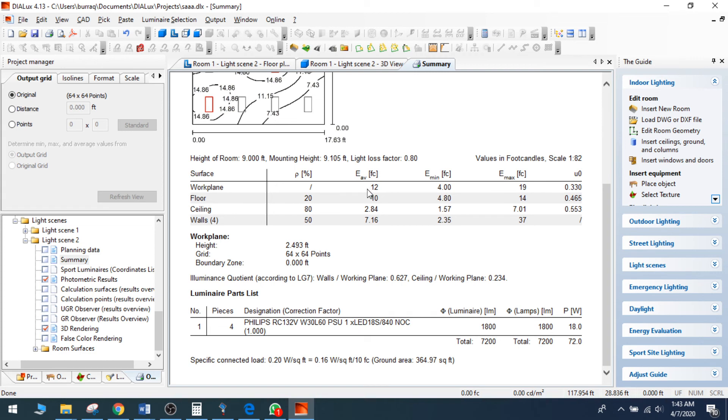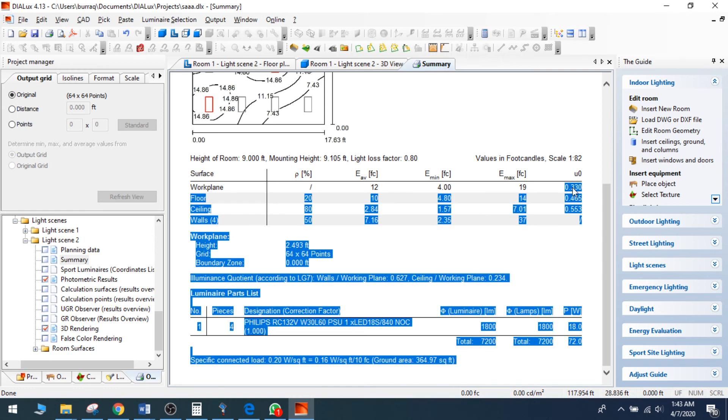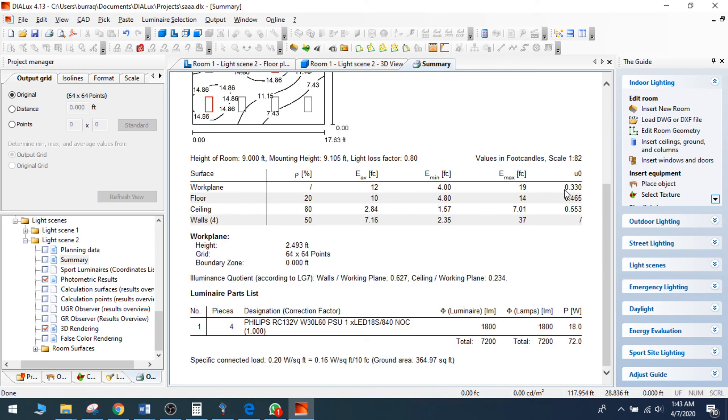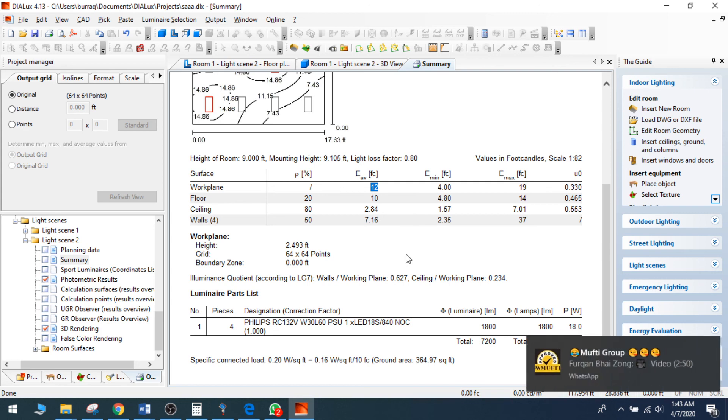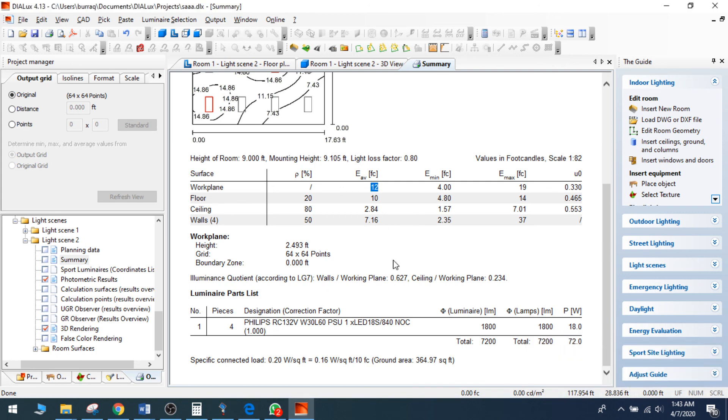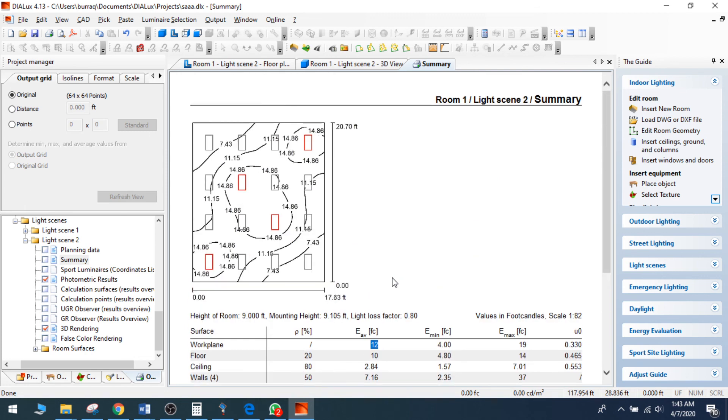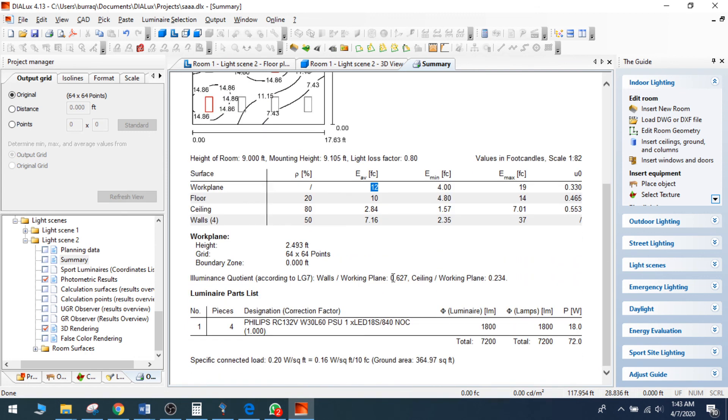It will provide me the lights I have to use for my emergency lighting design. This is basically a work plane E average is 12, so that's fine I think. And the uniformity doesn't matter for the emergency lighting design. You can check yet as per your requirement that uniformity is as per 25% or not of your actual room. So this is basically an emergency lighting design in DIALux. Thank you very much and we'll come with another lecture. Thank you.